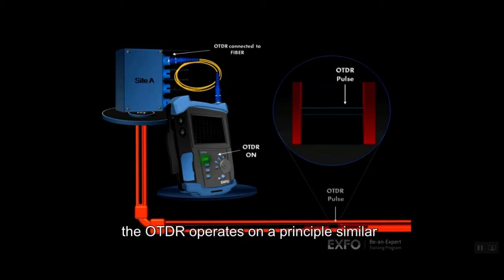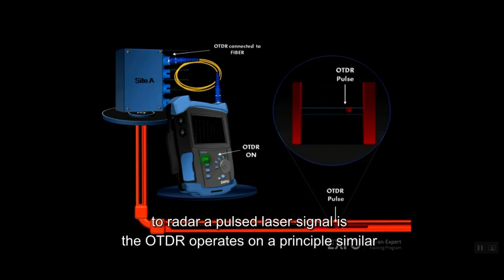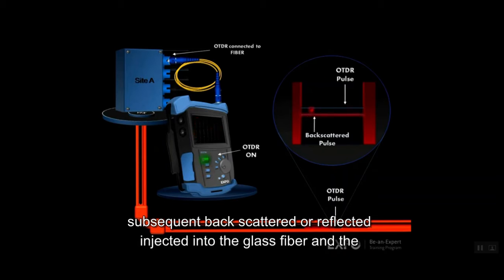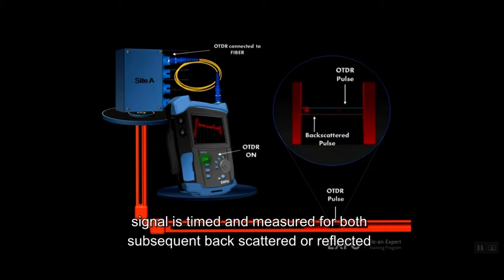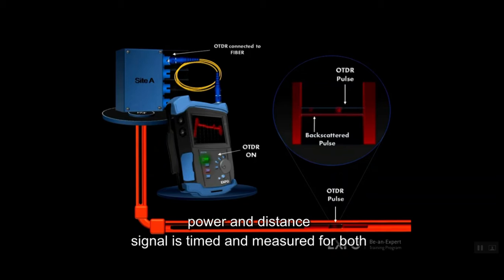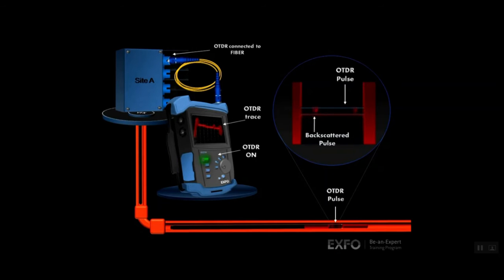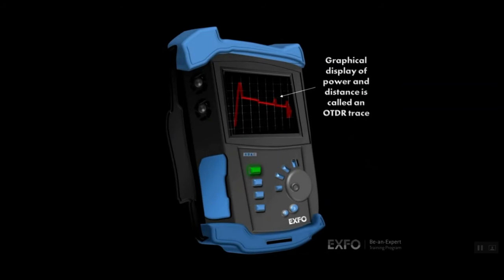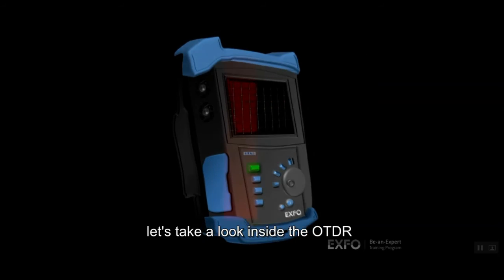The OTDR operates on a principle similar to radar. A pulsed laser signal is injected into the glass fiber and the subsequent backscattered or reflected signal is timed and measured for both power and distance. Let's take a look inside the OTDR.